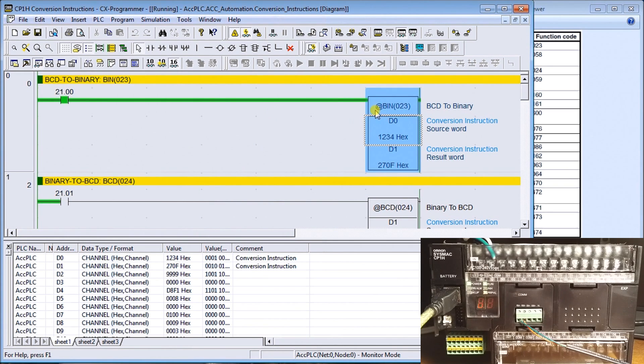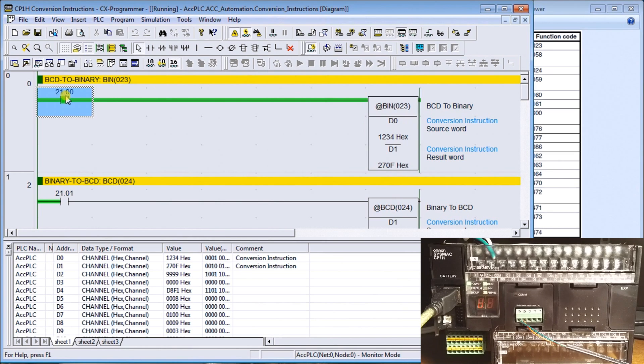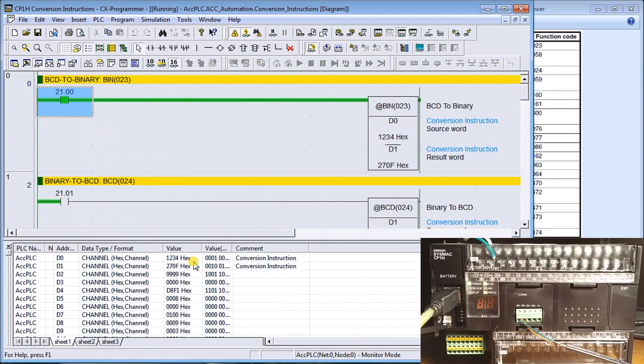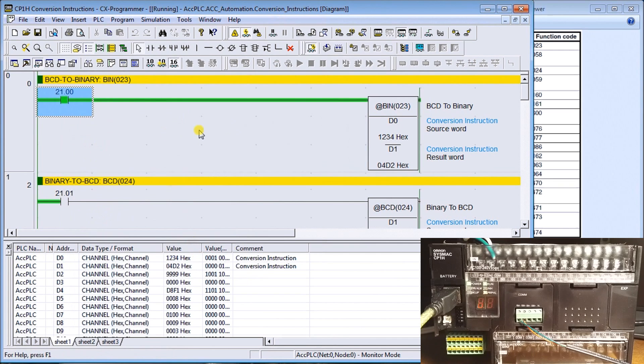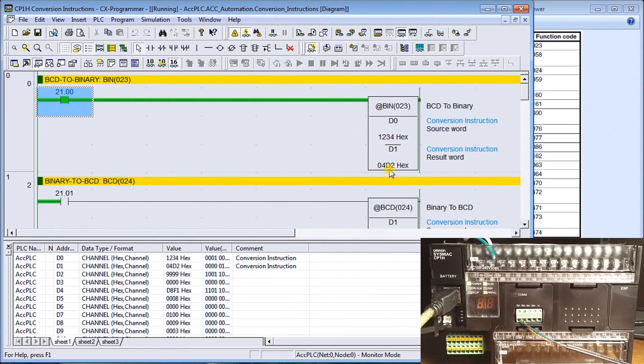You'll see that because my instruction here has the at sign in front of it, it only will do the translation on a transition from off to on. So if I set this back off again and then turn it back on, we will then have the conversion take place, which changes into 4D2 hex, which is the equivalent to 1234 BCD.